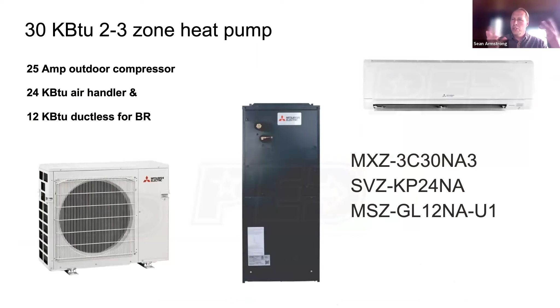Yep. And that would just have it running at its regular rated power for 16 hours. They can run even higher than their rated power, so it could finish the job in 12 hours, but there's still lots of slack in that peak day anyway. So that gives me confidence to be recommending a 2.5 ton heat pump. And so that's the 30,000 BTU rating on that.